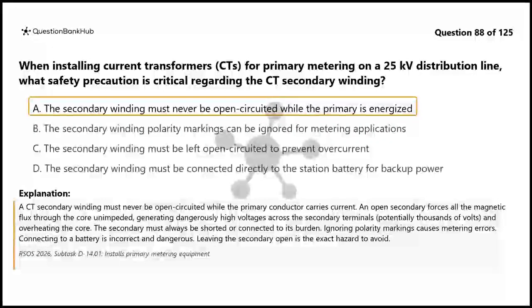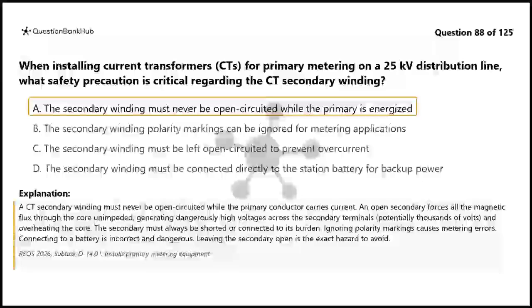An open secondary forces all the magnetic flux through the core unimpeded, generating dangerously high voltages across the secondary terminals, potentially thousands of volts, and overheating the core. The secondary must always be shorted or connected to its burden. Ignoring polarity markings causes metering errors. Connecting to a battery is incorrect and dangerous. Leaving the secondary open is the exact hazard to avoid.